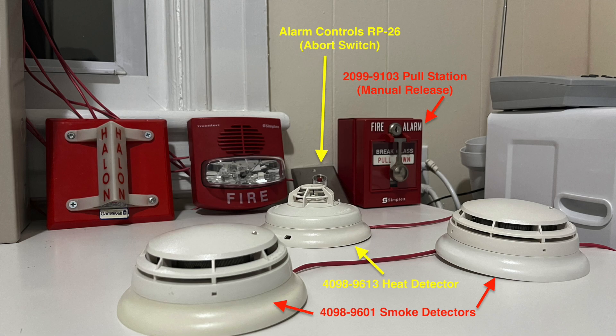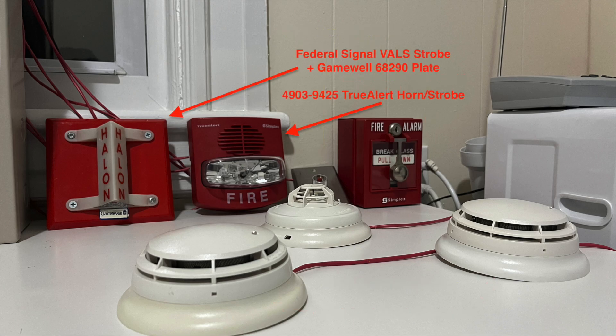and an Alarm Controls RP26 button as the abort switch. Simplex does have their own abort switches and manual release stations, I just don't have those. The notification appliance is a 4903-9425 TrueAlert horn strobe, set to free run because the 4004R does not have smart sync. For the releasing device we have a Federal Signal VALS strobe on a Gamewell strobe plate, which represents a releasing mechanism or solenoid that would release a suppression agent in a real system.